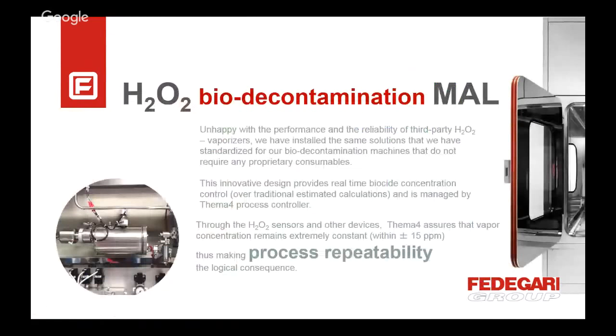Just a few words about our H2O2 biodecontamination material lock. We have developed this technology inside Fedegari. We have designed our own hydrogen peroxide generator. It is based on a dosing pump and a heated plate that vaporizes the droplets of hydrogen peroxide. And then through clean compressed air, this airstream, including the vapor of hydrogen peroxide, is delivered inside the chamber.